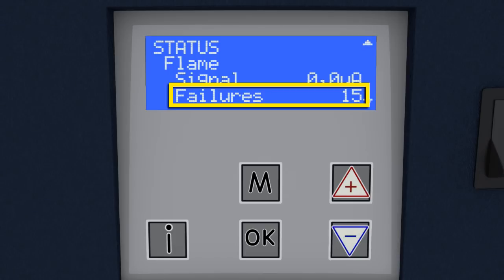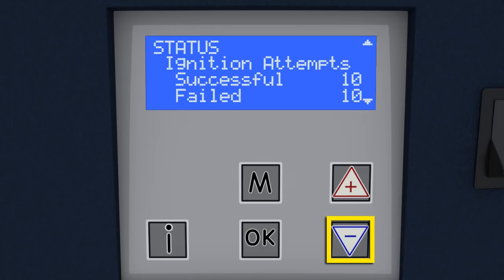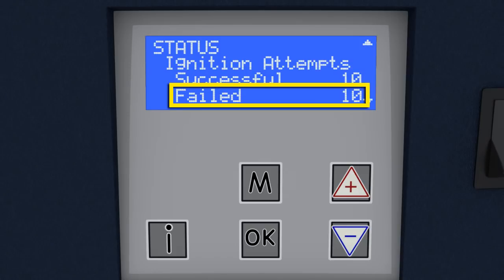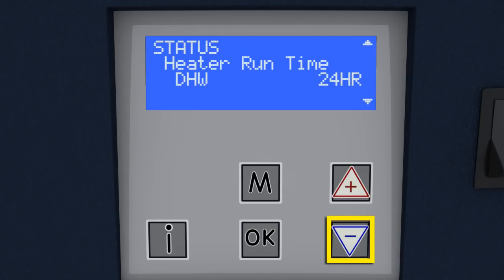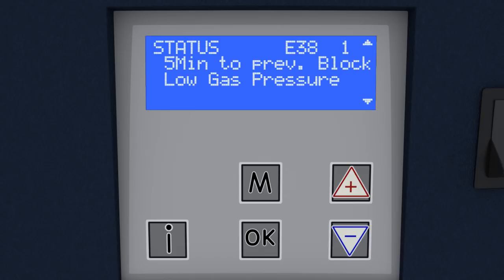A flame failure is defined as a loss of flame signal after the flame has been proven during a run cycle. Use the down arrow to advance to the history of ignition attempts. A running total of successful and failed attempts is listed. Use the down arrow to advance to the total hours of heating time for the water heater. Using the down arrow, the next screen displays the history of blocking errors. The time interval between errors is given in minutes, hours, days, and weeks as needed. To the right of the word status is the letter E, followed by the number of the error code. The error message is shown below the time interval.